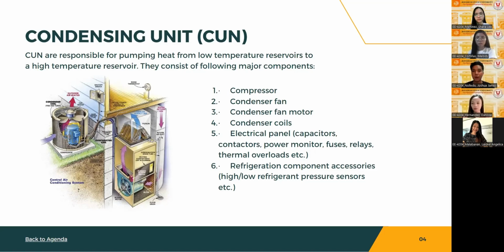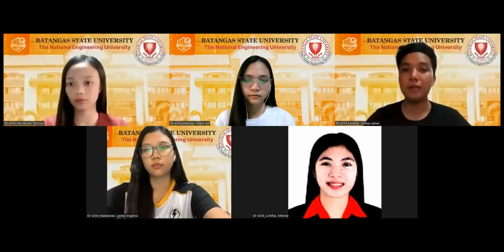The basis of working of a condensing unit is a simple vapor cycle. The gaseous refrigerant is pumped by the compressor such that it has a higher temperature than the surrounding atmosphere. This heated refrigerant is pumped to the condenser coil where forced air ventilation by the condenser fan motor allows the refrigerant to reject heat to the surroundings. The refrigerant rejects all the latent heat and becomes saturated liquid. This liquid is throttled to a low temperature and pumped into the AHU where it cools the surrounding air by absorbing the heat and becomes saturated vapor. This vapor is then passed to the compressor and the cycle continues.